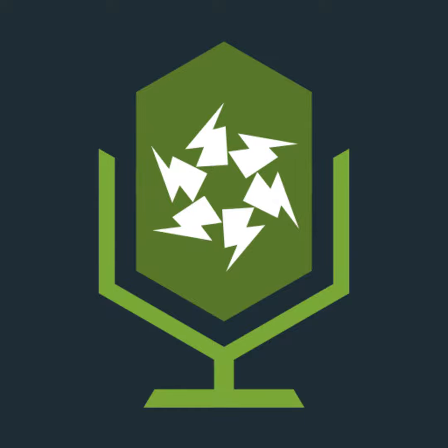Okay, so let's remember that all these protective measures, including ADS, have to achieve basic and fault protection. And with regards to the basic protection, that was the insulation, the barriers, the enclosures. The fault protection was the combination of earthing, bonding, and the selection of a suitable protective device, which is what this is. That's why it says fault protection.